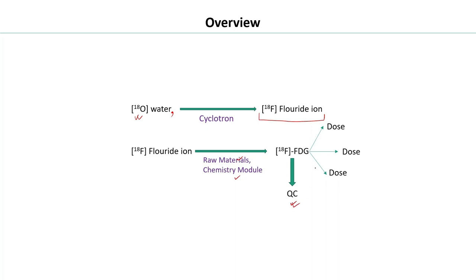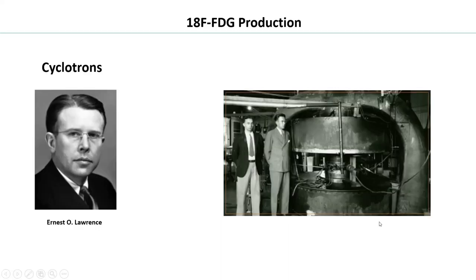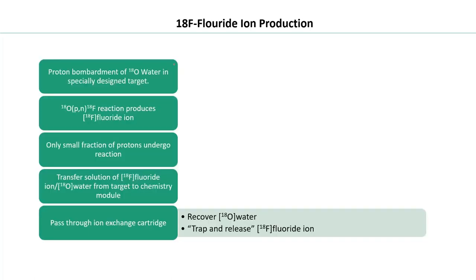A key ingredient for FDG production is a particle accelerator. Ernest Lawrence developed the first cyclotron at the University of California, Berkeley, and was awarded the Nobel Prize in Physics for this achievement. The cyclotron accelerates charged particles like protons, electrons, and alpha particles to very high velocities. Medical cyclotrons accelerate protons to a range of 11 to 17 mega-electron volts for FDG production.